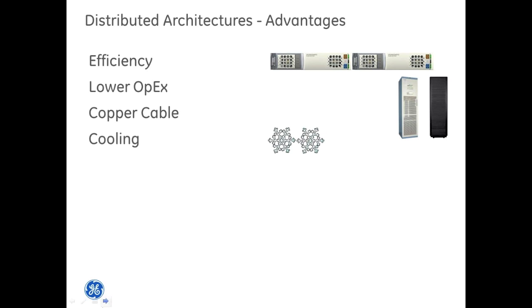Cooling. I have a reduction in cooling capacity, or cooling needs, because I'm generating less heat from improved efficiency and decreased losses. Flexible energy reserve. This is my ability to provide only the reserve that's needed by the particular equipment. I don't have to provide 8 hours for the entire facility.